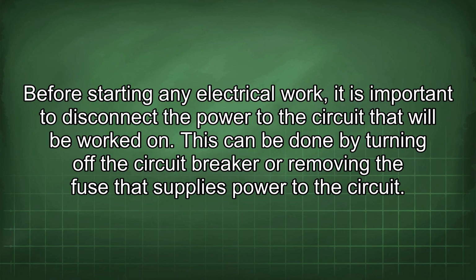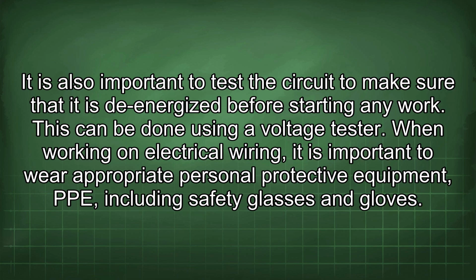Before starting any electrical work, it is important to disconnect the power to the circuit that will be worked on. This can be done by turning off the circuit breaker or removing the fuse that supplies power to the circuit. It is also important to test the circuit to make sure that it is de-energized before starting any work. This can be done using a voltage tester.